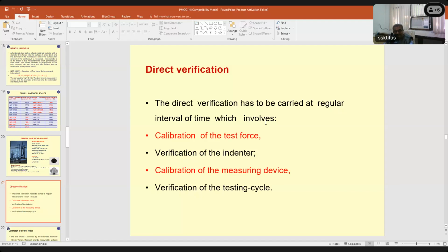And if your machine is used more frequently and in a more rugged way, then you have to check the hardness value, or the performance of the machine, using standard blocks every now and then as per your use. Now the direct verification has to be carried out at regular intervals, and it involves the calibration of the test force, because force is a component which you already saw. And the second thing is verification of the indenter.